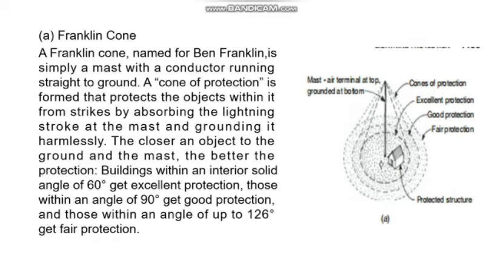First example of lightning protection is Franklin cone. A Franklin cone, named for Ben Franklin, is simply a mast with a conductor running straight to ground. A cone of protection is formed that protects the objects within it from strikes by absorbing the lightning stroke at the mast and grounding it harmlessly. The closer an object to the ground and the mast, the better the protection. So buildings within an interior solid angle of 60 degrees get excellent protection, and those within an angle of 90 degrees get good protection, and those within an angle of up to 126 degrees get fair protection.